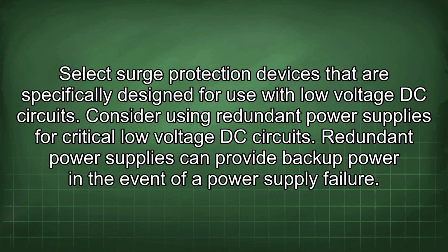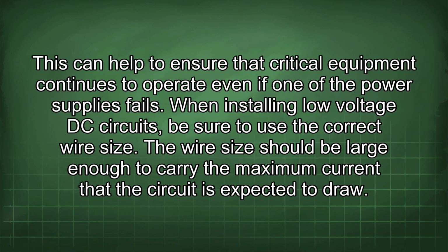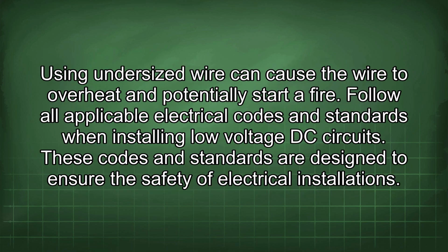Consider using redundant power supplies for critical low-voltage DC circuits. Redundant power supplies can provide backup power in the event of a power supply failure. This can help to ensure that critical equipment continues to operate even if one of the power supplies fails. When installing low-voltage DC circuits, be sure to use the correct wire size. The wire size should be large enough to carry the maximum current that the circuit is expected to draw. Using undersized wire can cause the wire to overheat and potentially start a fire.